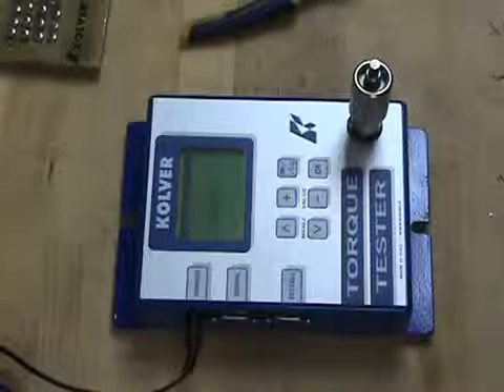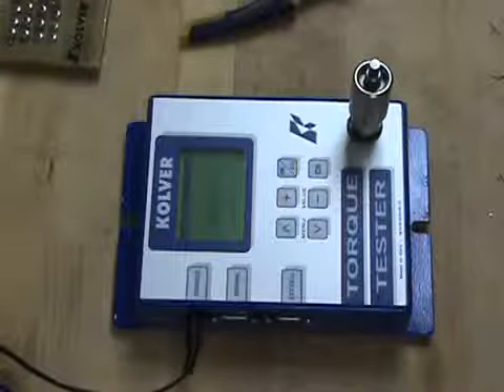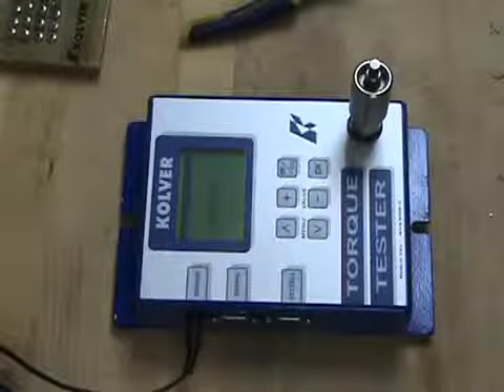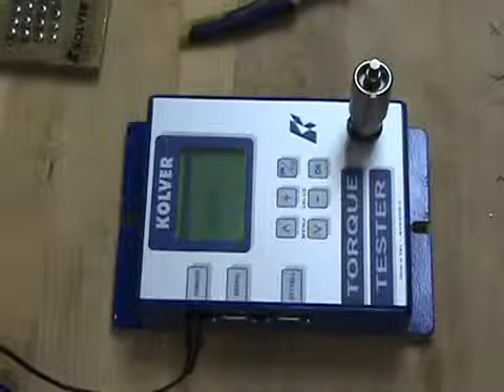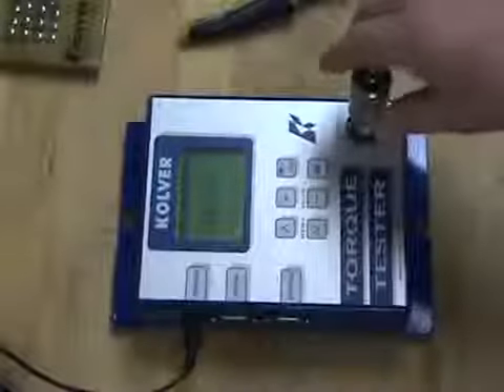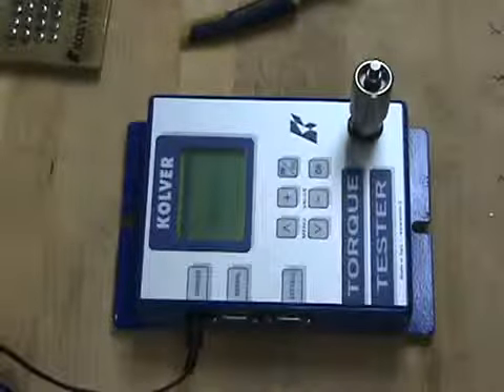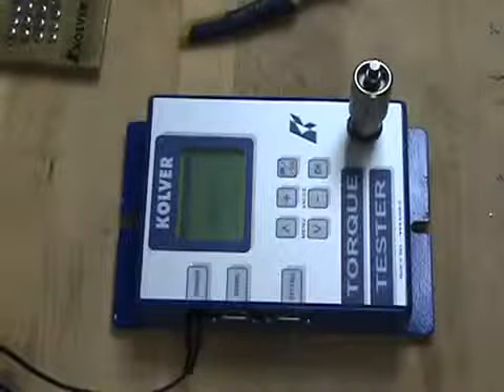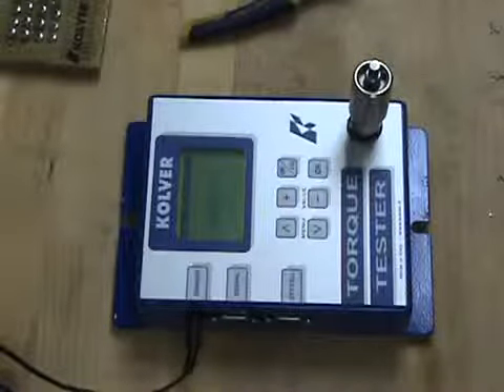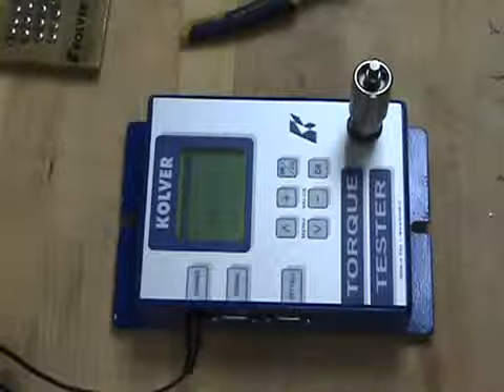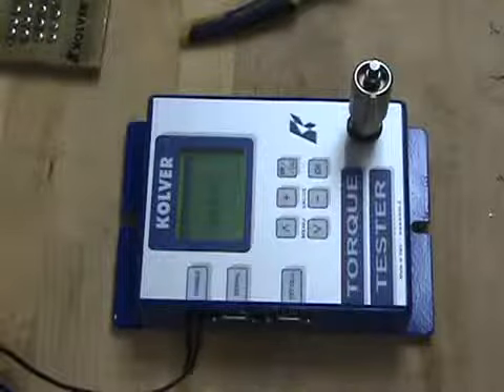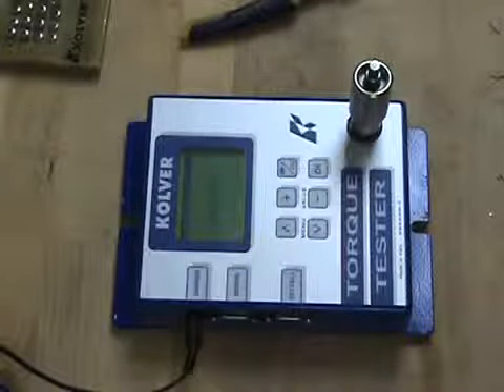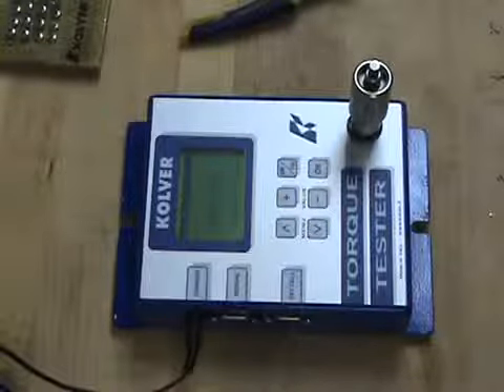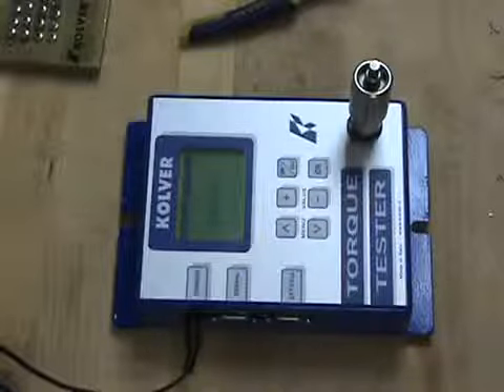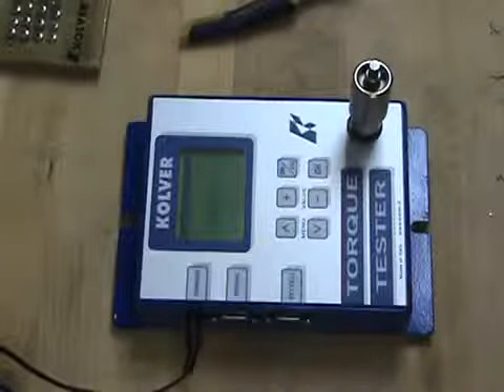And an important feature is the threshold. If you have your threshold very, very low, to the point of 0 or 0.1, you're going to read numbers that are possibly erroneous, because you can almost touch this and get 0.1 inch-pounds, and those will interfere with your actual readings. So I would suggest your threshold be at least 0.4 inch-pounds for this particular unit. If you have a K20, the low end of that unit is around 4 inch-pounds. You don't want your threshold to be at 0.5 or lower, because the unit's not supposed to be reading down there anyway, and you will end up with erroneous numbers.